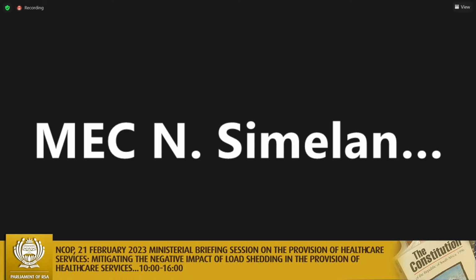As a result of load shedding, the waiting time for MRI scans has increased to approximately 12 months, because when there is an outage, there is no MRI service. Only ultrasounds function during load shedding. These bedside units, which are rechargeable, are used for as long as there is battery life.